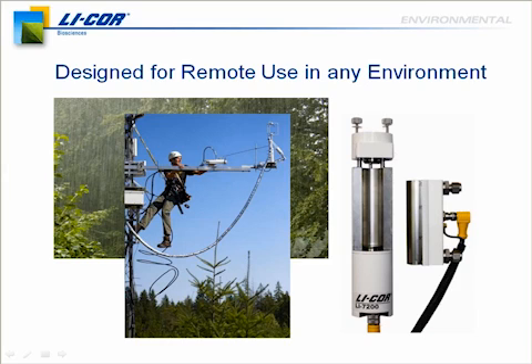So when we say you can put the analyzer at the top of the tower and have a short intake tube, that's true, and you don't have to worry about enclosing it at the top of the tower because it was designed to be placed there without an enclosure. So thanks for asking that. It's good to clarify and make sure that's clear to people. You're not going to need to try to elevate your enclosure because now you don't need an enclosure for the 7200.